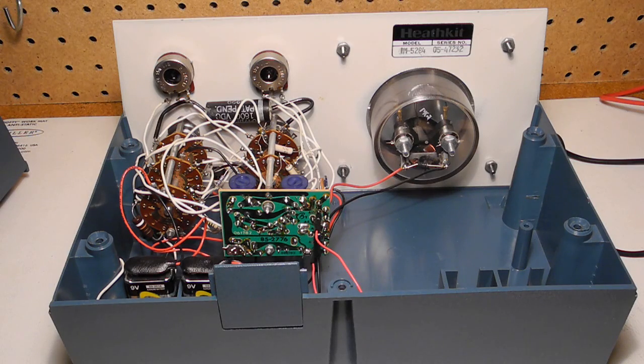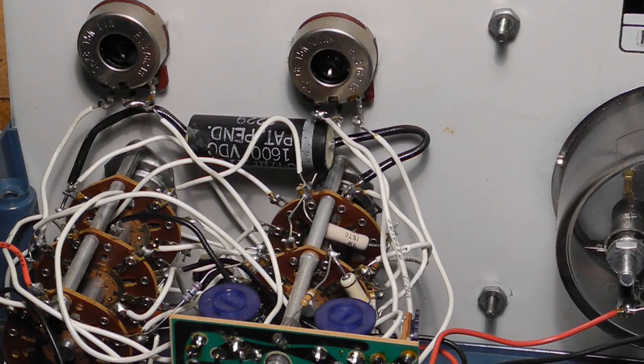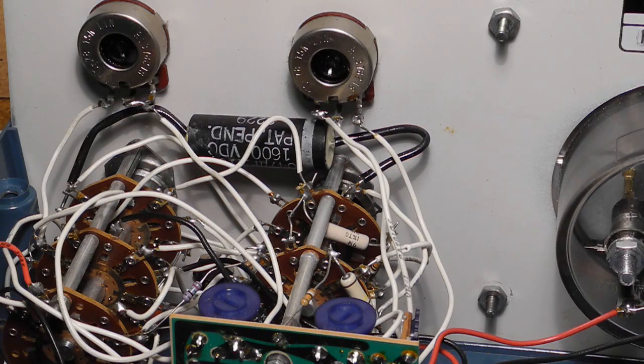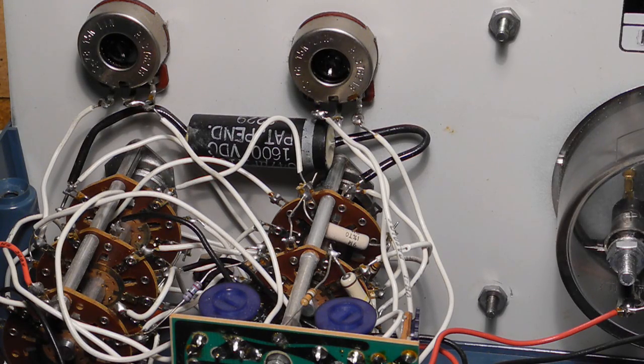I cleaned the unit and ran through the calibration procedure. After doing this, it seemed to be quite accurate on all functions and ranges. In the future, I may replace the large paper cap as it may have become electrically leaky, but I think I'll wait until I receive the manual and run through the whole assembly procedure.